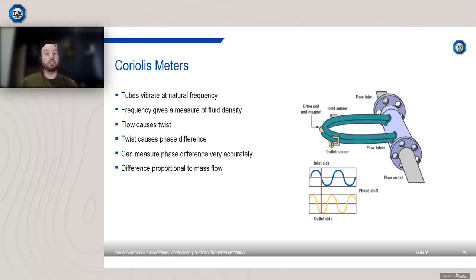Well, the first advantage is they can give you a measure of fluid density. So how do they measure density? Well, typically a Coriolis meter will have one or two flow tubes, and these tubes are vibrated at a natural frequency. And by measuring the frequency, you can then determine the fluid density, because the frequency depends on the mass of the tubes, and when the density of the fluid changes, the total mass contained within the tubes changes. So, first big advantage, they give you a measure of fluid density.